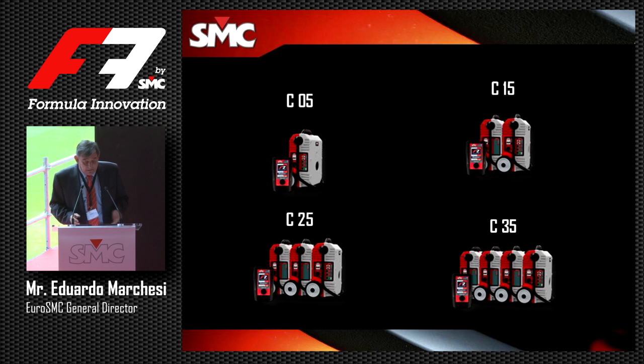The most typical configuration, the one we hope or expect to have, is the C15, because it combines both good worlds. The master also makes a part of injecting current by itself. We are able to make a current transformer knee point test, power transformer TTR, saturation tests, and more tests that the master is able to do.